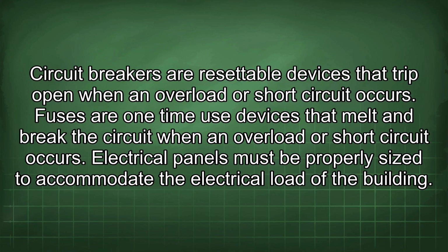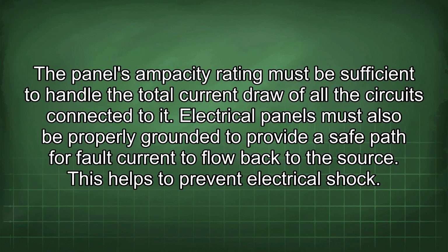Electrical panels must be properly sized to accommodate the electrical load of the building. The panel's ampacity rating must be sufficient to handle the total current draw of all the circuits connected to it. Electrical panels must also be properly grounded to provide a safe path for fault current to flow back to the source. This helps to prevent electrical shock.